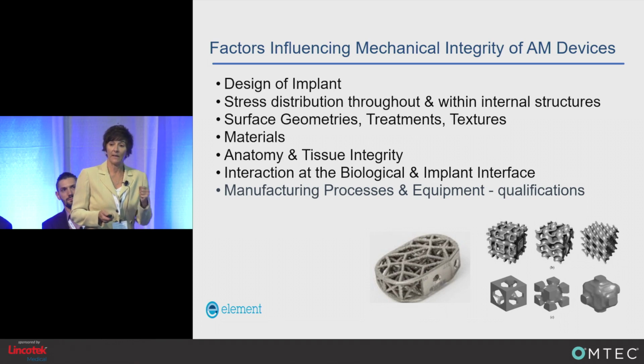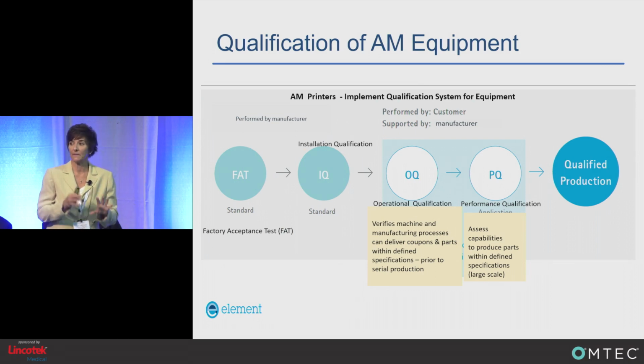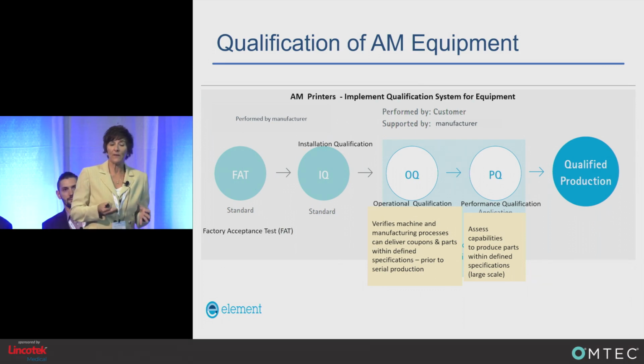And understand and validate your manufacturing processes and equipment, and have a robust quality system. So just talking about the quality system very briefly is, first you have to qualify that equipment as part of that system. And we do that through an IQ, OQ, PQ system where you have your installation qualification, your operational qualification. Can you produce samples to spec? And then can you scale up to much larger supply?